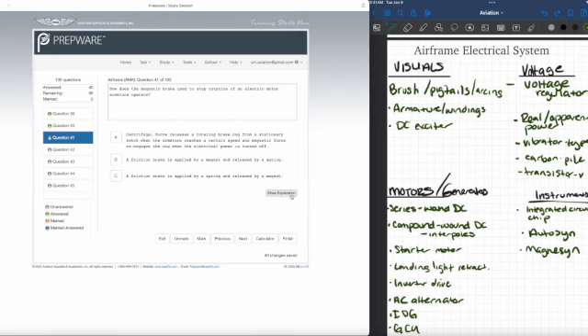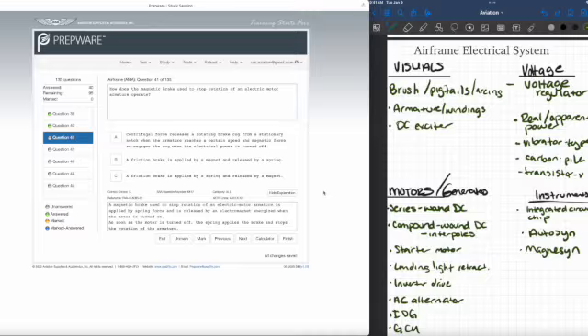So, how does the magnetic brake used to stop rotation of an electric motor armature operate? A friction brake is applied by a spring and released by a magnet. A magnet brake used to stop rotation of an electric motor armature is applied by spring force and is released by an electromagnet energized when the motor is turned on. As soon as the motor is turned off, the spring applies the brake and stops the rotation of the armature. So here we're going to write down the spring as well.